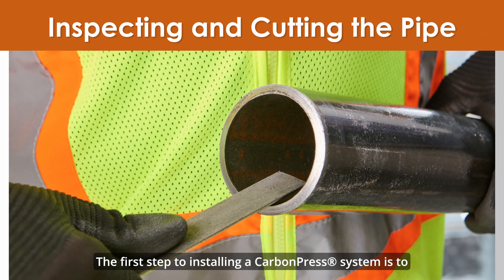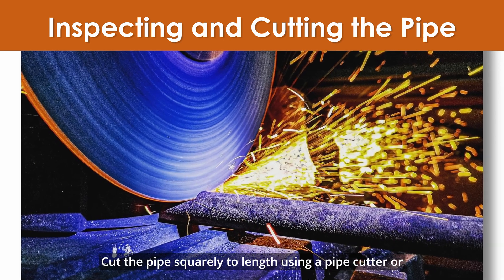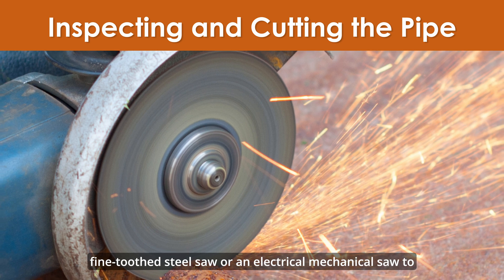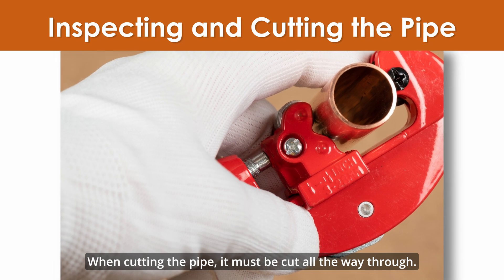The first step to installing a CarbonPress system is to inspect the pipe for imperfections and cut the pipe. Cut the pipe squarely to length using a pipe cutter, fine-toothed steel saw, or an electrical mechanical saw to avoid jagged edges or scratching the pipe's surface. When cutting the pipe, it must be cut all the way through.